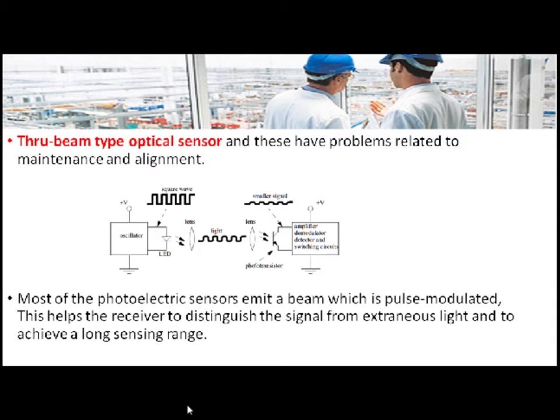The advantage of using a modulated signal is that the receiver can distinguish this modulated signal from extraneous light like fluorescent light or direct sunlight. This improves the noise immunity of the sensor and also increases the sensing range of the detector.